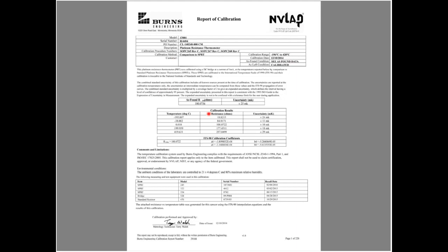And then we have the as found information. This particular one shows that at the 0 degree C point, the uncertainty was 25 millikelvins, and it was done from minus 196, which is liquid nitrogen, up to about 420 degrees C, and all the associated uncertainties that go with it.